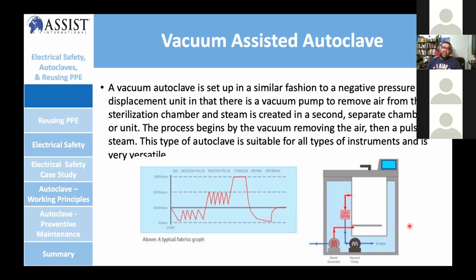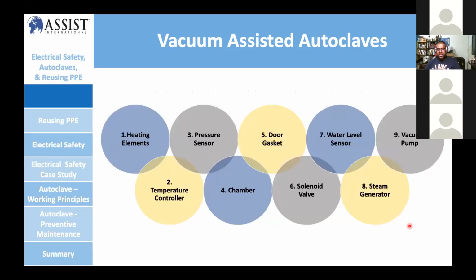When you talk about a vacuum assist autoclave, you need to know that there's a heating element, temperature control, pressure sensor, the chamber, door gasket, all that, and solenoid valve, water level sensor, steam generator, vacuum pump. These are the 9 types of components that you can normally see inside a vacuum assist autoclave. So the 9 types of components you can see very clearly.